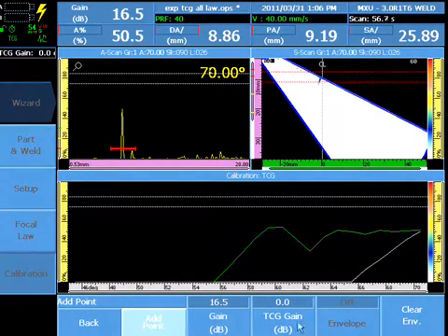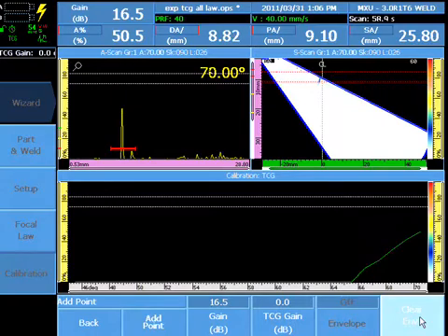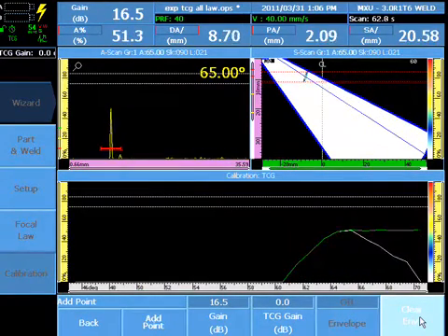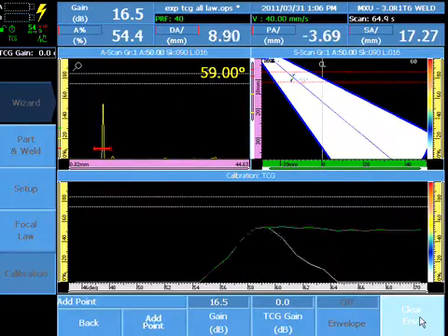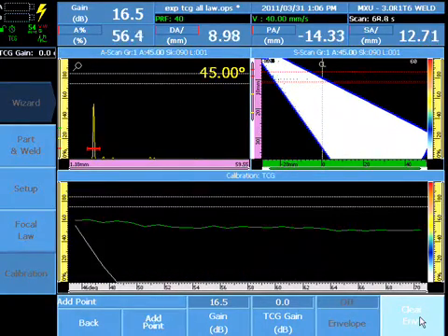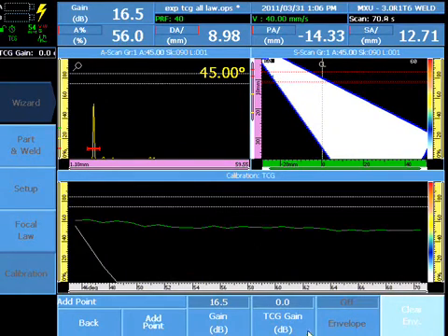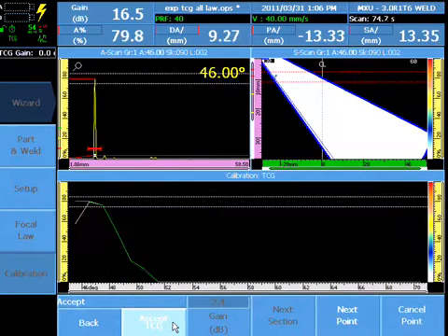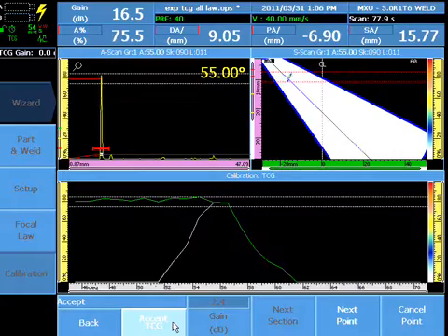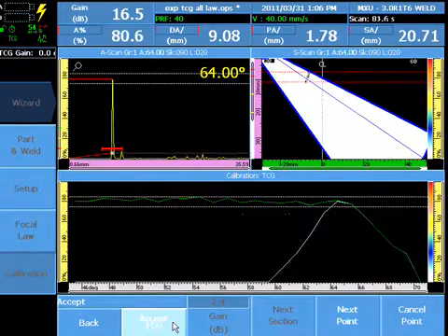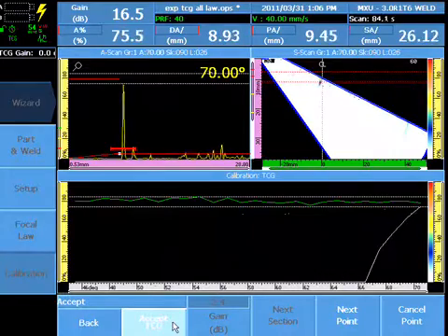Clear the envelope and move the probe so that every focal law is exposed to the calibration target. Add the point and the software will make an adjustment. Check the point to ensure that the calibration calculated is in the range of your tolerance for every focal law.